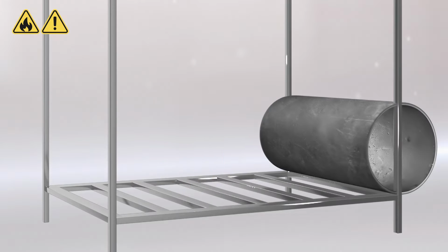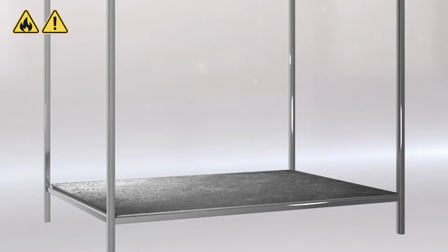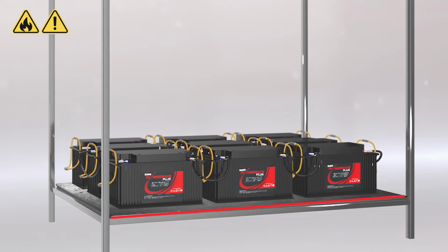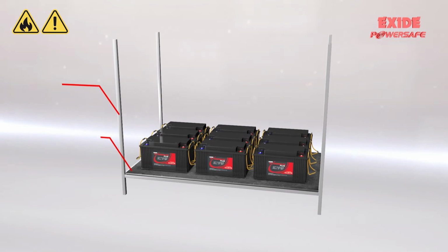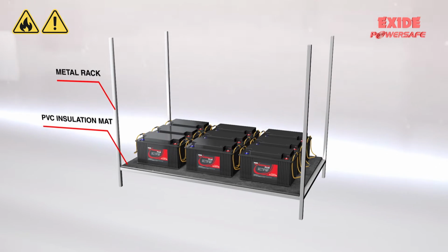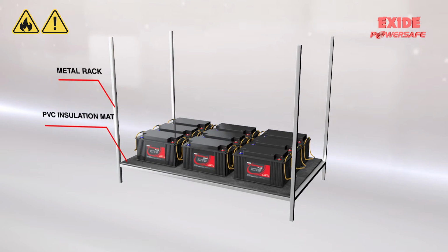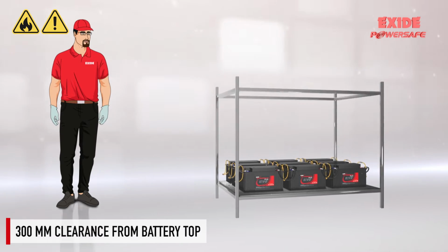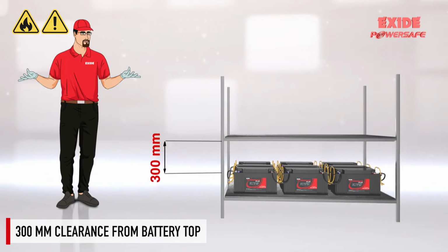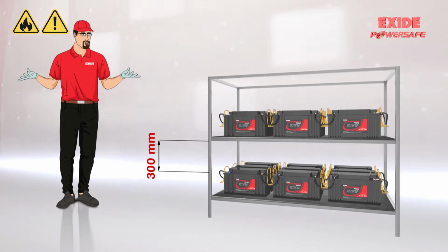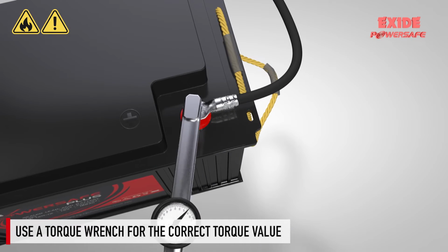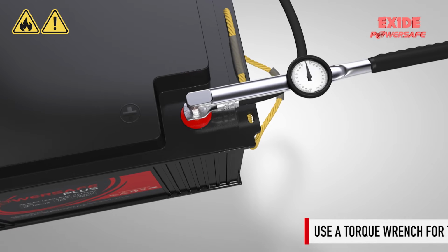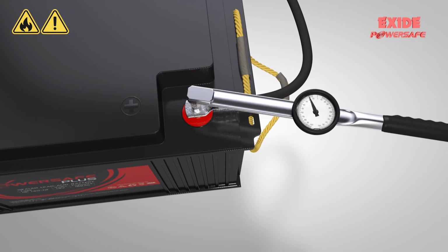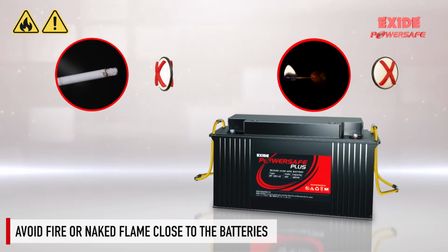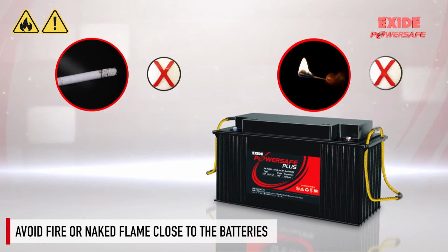Fifth, it is strongly recommended that an insulating material such as a PVC mat be placed between the battery and the metal rack. The thickness of the insulation material must be such that it can withstand the DC voltage of the system without dielectric breakdown. Sixth, the racks should have at least 300 mm clearance from the battery top for easy access during maintenance work like cleaning and terminal tightening. A torque wrench must be used to tighten the terminals to the correct torque value during installation, and adhering to this practice is strongly recommended. And finally, one must ensure that no fire or naked flame is in close proximity to the batteries.